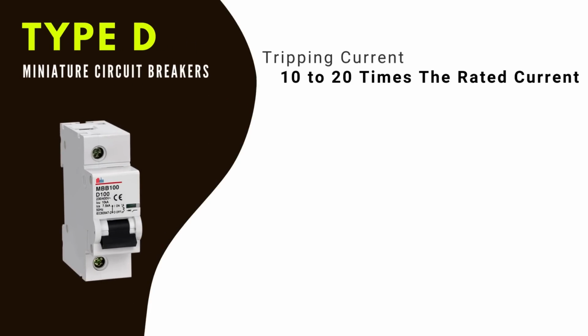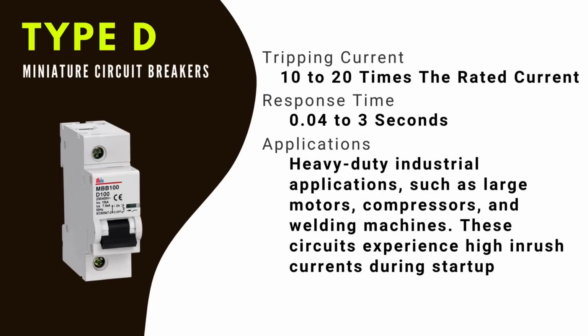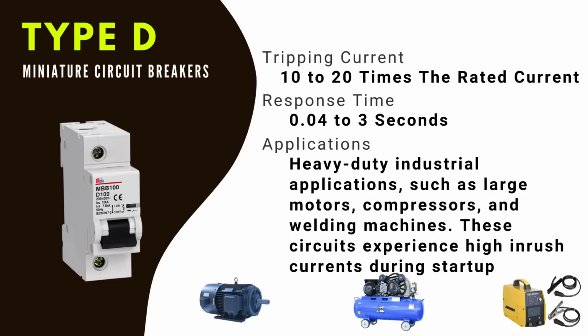Moving on to Type D MCBs. These have a higher tripping current, ranging from 10 to 20 times the rated current. With a tripping time of 0.04 to 3 seconds, they're perfect for heavy-duty industrial applications, such as large motors, compressors, and welding machines. These circuits experience high inrush currents during startup, so Type D MCBs provide the necessary protection.